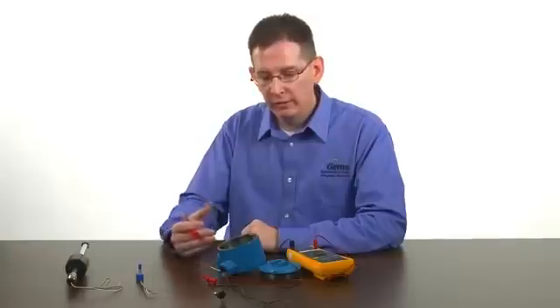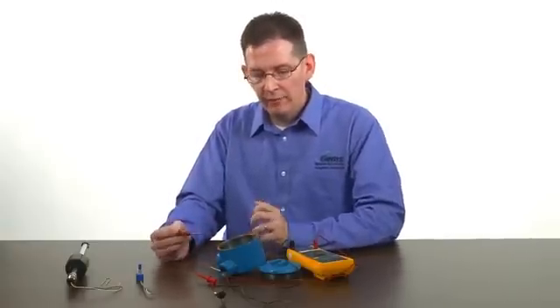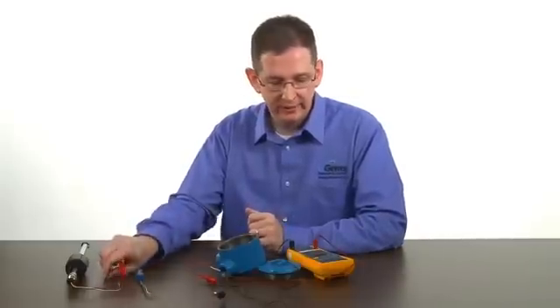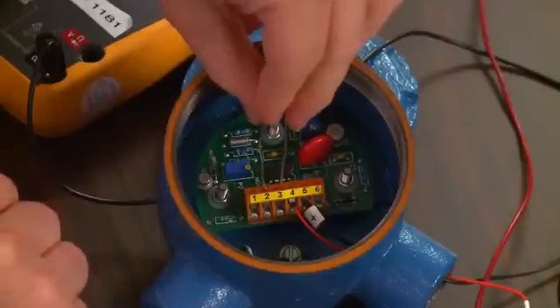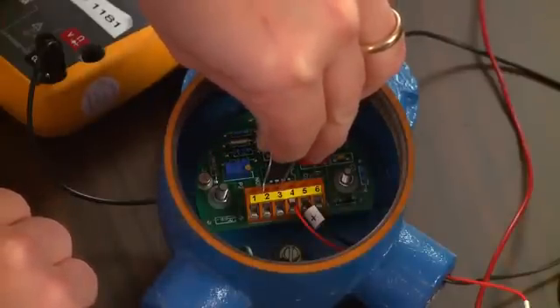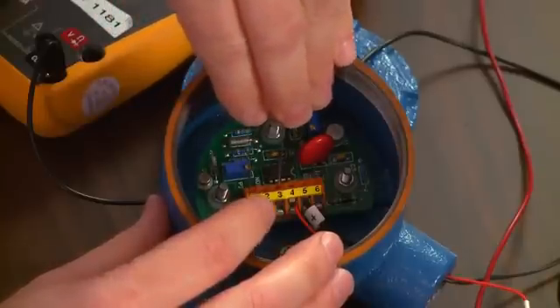Once you're done, your unit is fully calibrated. If you do not have a potentiometer handy, you can replace that by using a simple jumper wire, placing it from terminals 2 and 3 to set your 4 milliamp point and 1 and 3 to set your 20 milliamp point.